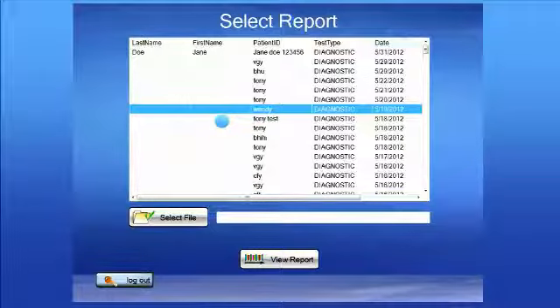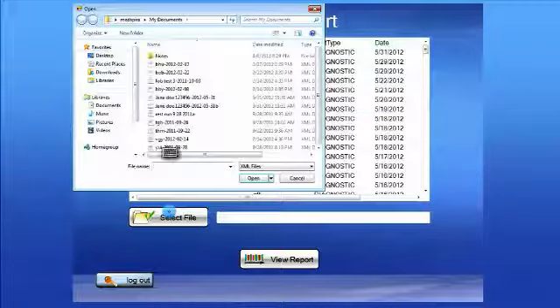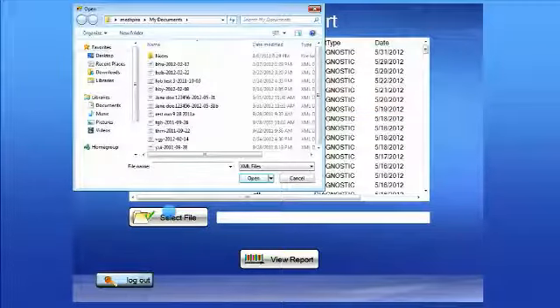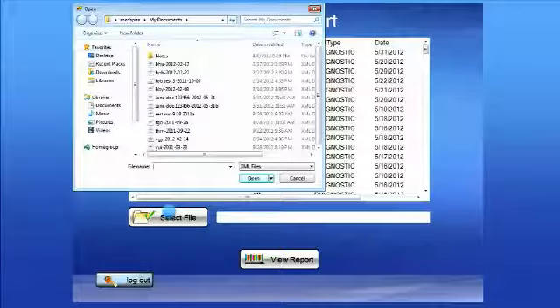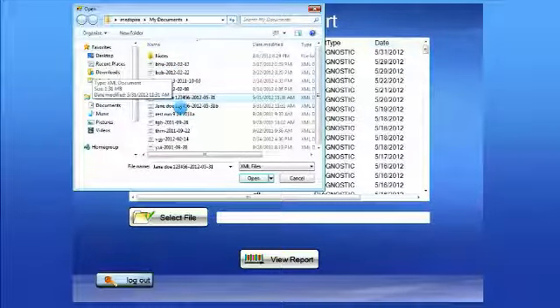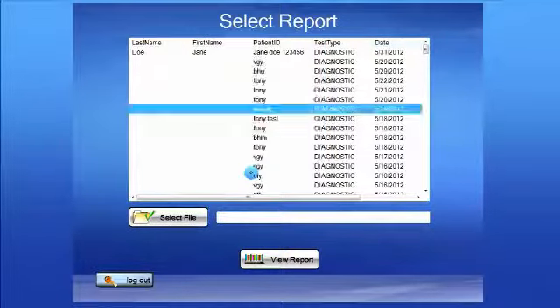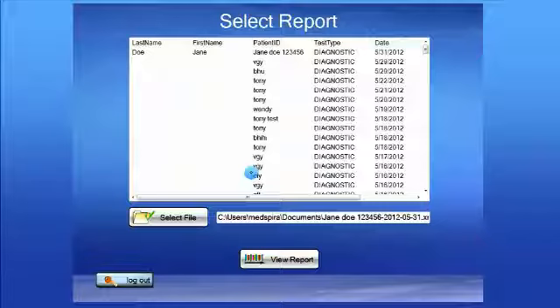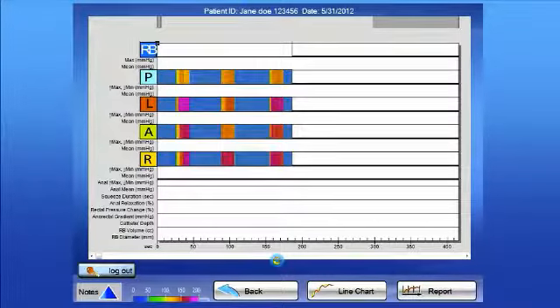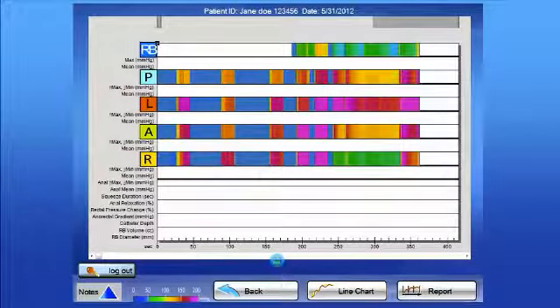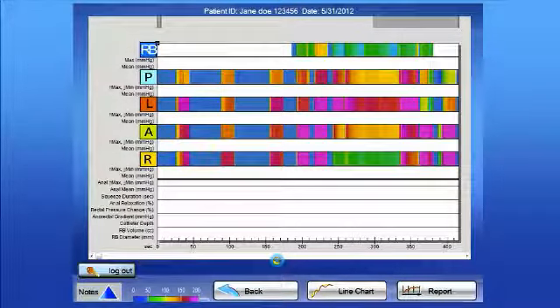If it happens to be a report that's been either emailed to you in encrypted form or is in a different folder than the one that's standard on the tablet PC, for example, the file is on a shared server, then you hit select file. And then it goes to the standard Windows library where you can find the folder that contains that particular test. You can pick up that test, highlight it, and hit open. It will load into the open space. Tap view report and up comes that report from that particular file.